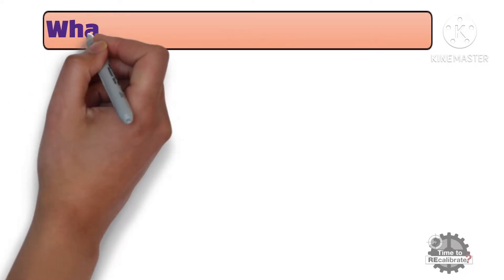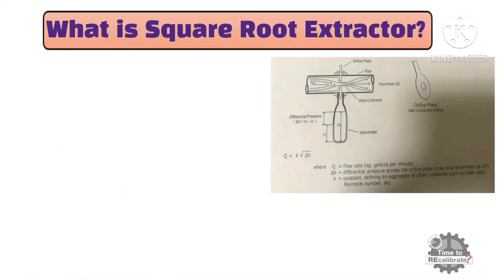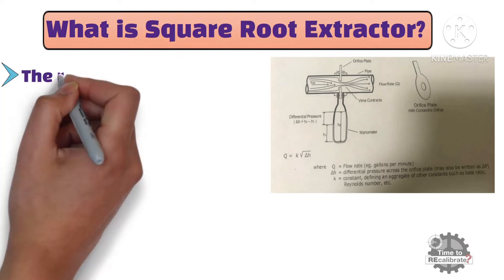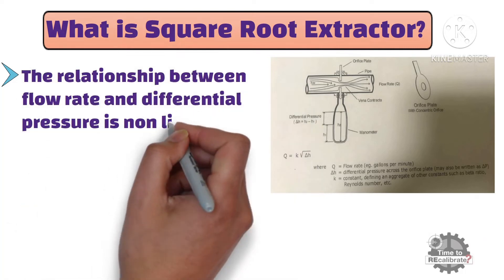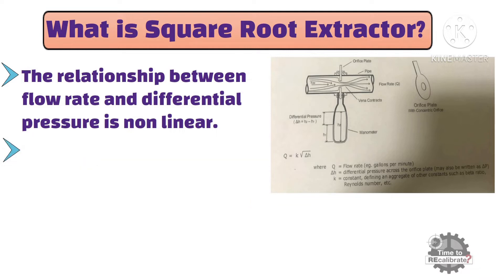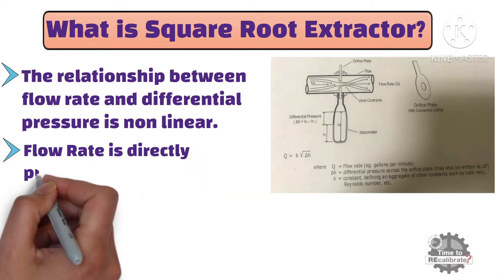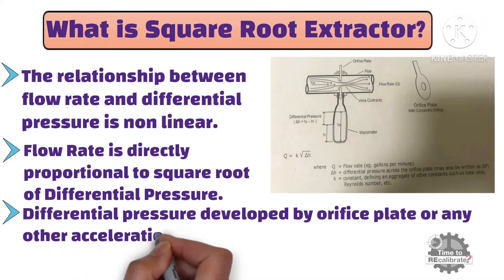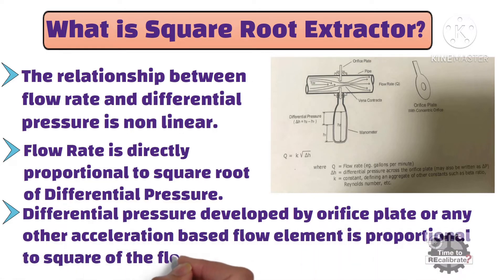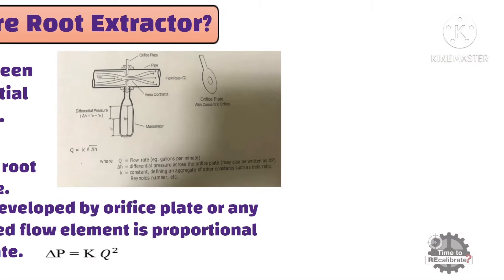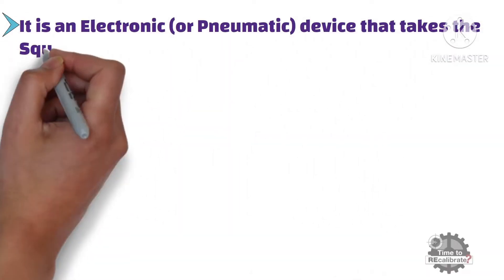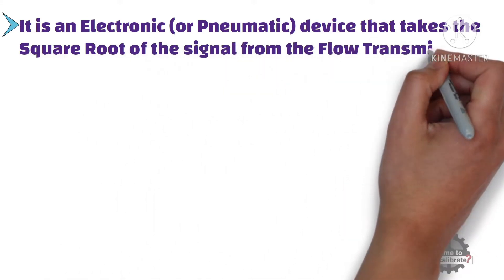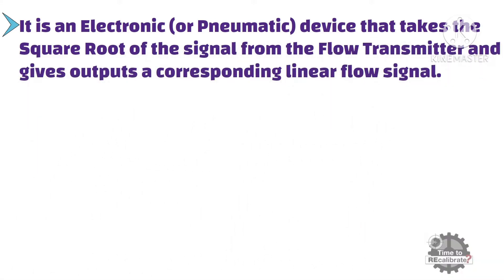First of all, what is a square root extractor? As we know, the relationship between flow rate and differential pressure is non-linear. In other words, flow rate is directly proportional to the square root of differential pressure. Or we can say that the differential pressure developed by an orifice plate or any other acceleration-based flow element is proportional to the square of the flow rate. So, a square root extractor is an electronic or pneumatic device that takes the square root of the signal from the flow transmitter and produces an output corresponding to a linear flow signal.